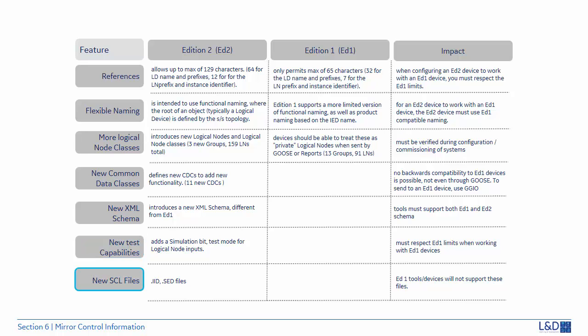Finally, in Edition 2, new substation configuration language files were introduced: the IID, the Instantiated IED Description File, and the SED, the System Exchange Description File, which are not supported by Edition 1.